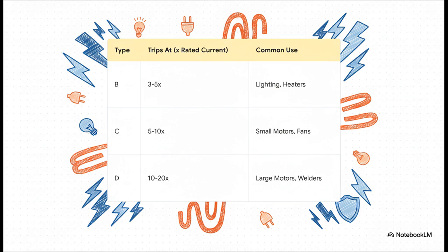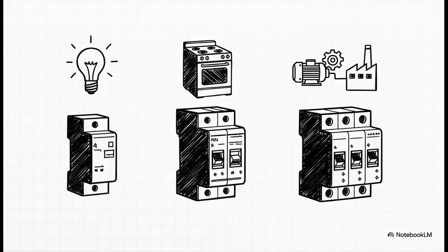The whole point is you have to match the breaker to the job to get the right balance of protection and performance. And it's not just about sensitivity either. They also come in different shapes and sizes, from a single pole breaker protecting one simple circuit to a double pole for a big appliance like a stove, all the way up to 3 and 4 pole breakers for complex industrial power. It's an incredibly scalable system of protection, tailored for just about any need you can think of.